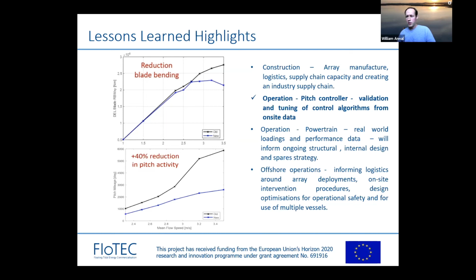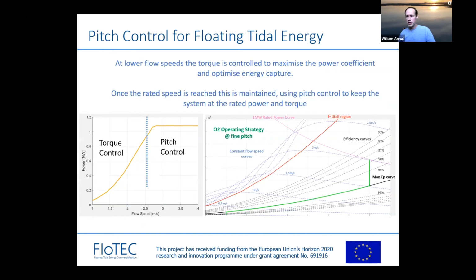All this work has been done using on-site data from the point of installation until now, and we're still continually doing that exercise. This slide shows how the controller uses torque control at lower speeds and then switches to pitch control as we approach rated power and beyond, and this functionality has been validated during ongoing generation activity.